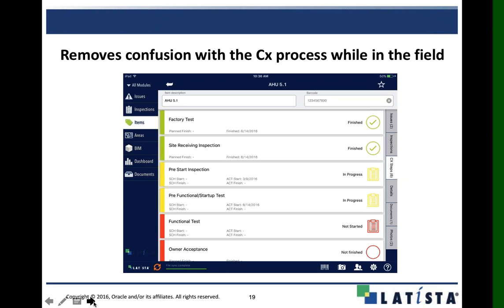It can all be provided to them on that system and on an individual basis as well. Josh, do you have input on this? It's idiot-proof. In commissioning, when we have different crews — sometimes multiple crews and different trades in the field trying to go through a procedure or checklist — before we start anything up, for example doing torquing, insulation resistance testing, testing breakers, testing bus, the screen before you is a color-coded system.